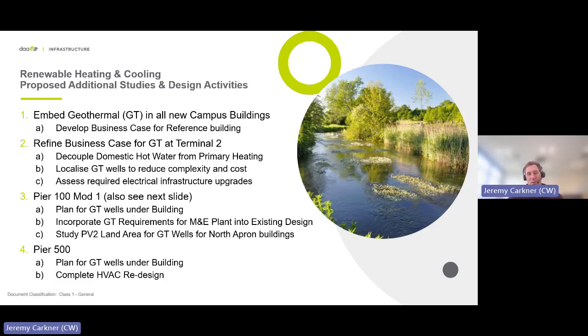At the same time, one recommendation from the systems design by GeoServe was to decouple domestic hot water from primary heating. We'd been thinking about this for a while at the airport, for some buildings and for T2. That project has now started, and it will help reduce flow and return temperatures for our heating and cooling, because right now we're servicing hot water, heating, and cooling from the same boiler. If we can decouple that, we can introduce lower flow and return temperatures, which has a more beneficial impact on geothermal.